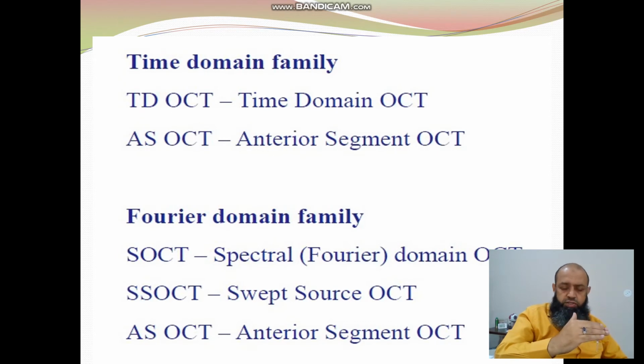And in Fourier domain technology, the spectrum, the light, the signal which transmits from the SLD and then it receives back, the actual signal versus the signal which we receive is being interpreted by the processor, and then we get the image.